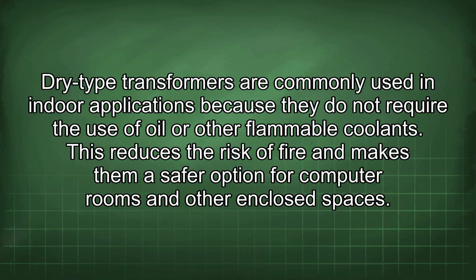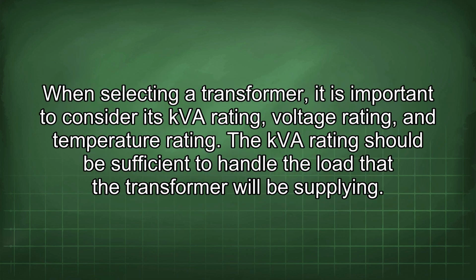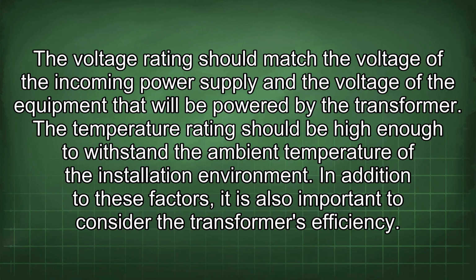Dry-type transformers are commonly used in indoor applications because they do not require the use of oil or other flammable coolants. This reduces the risk of fire and makes them a safer option for computer rooms and other enclosed spaces. When selecting a transformer, it is important to consider its kVA rating, voltage rating, and temperature rating. The kVA rating should be sufficient to handle the load that the transformer will be supplying. The voltage rating should match the voltage of the incoming power supply and the voltage of the equipment that will be powered by the transformer. The temperature rating should be high enough to withstand the ambient temperature of the installation environment.